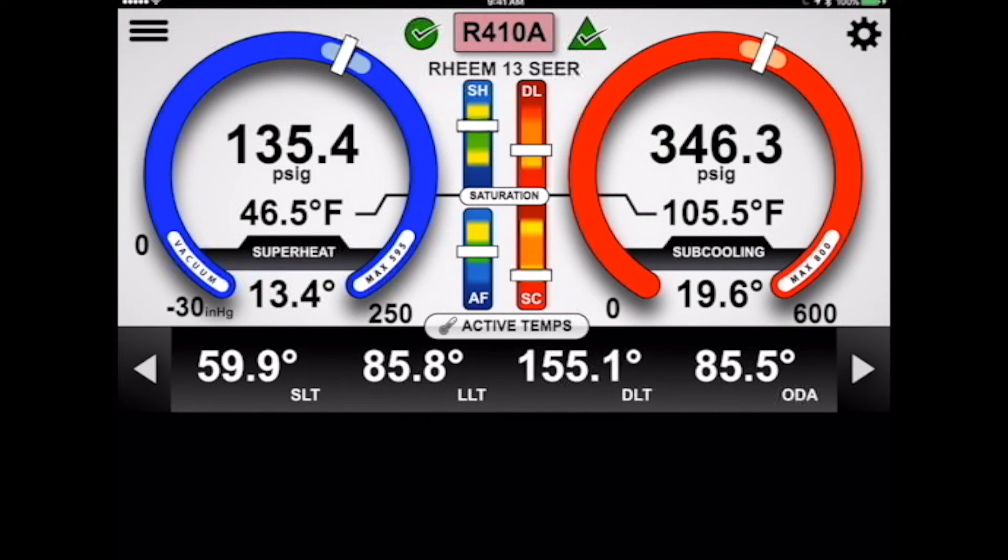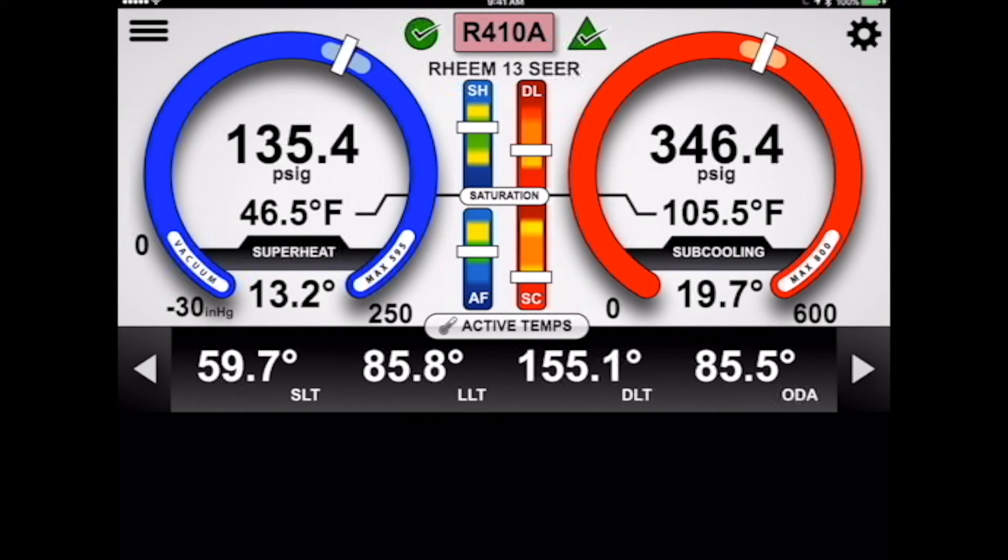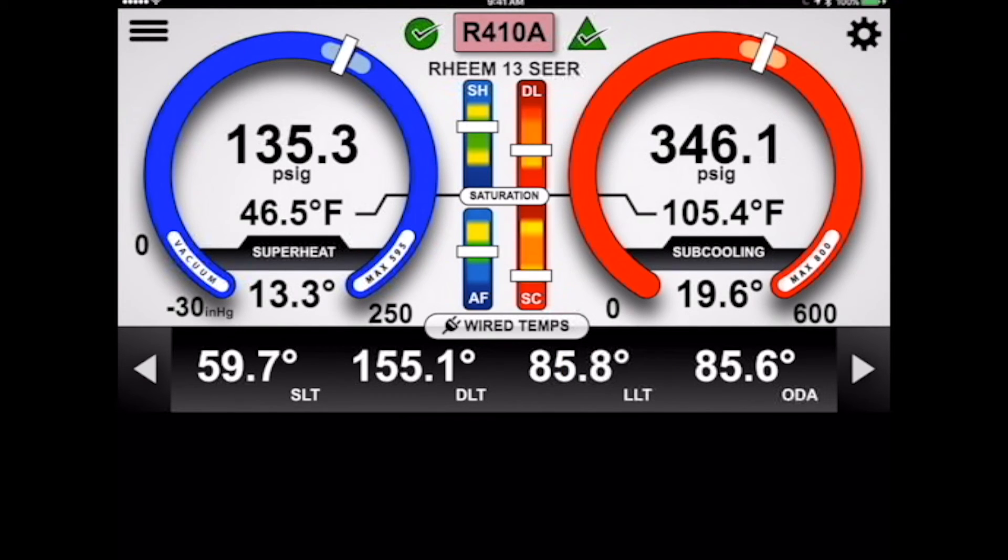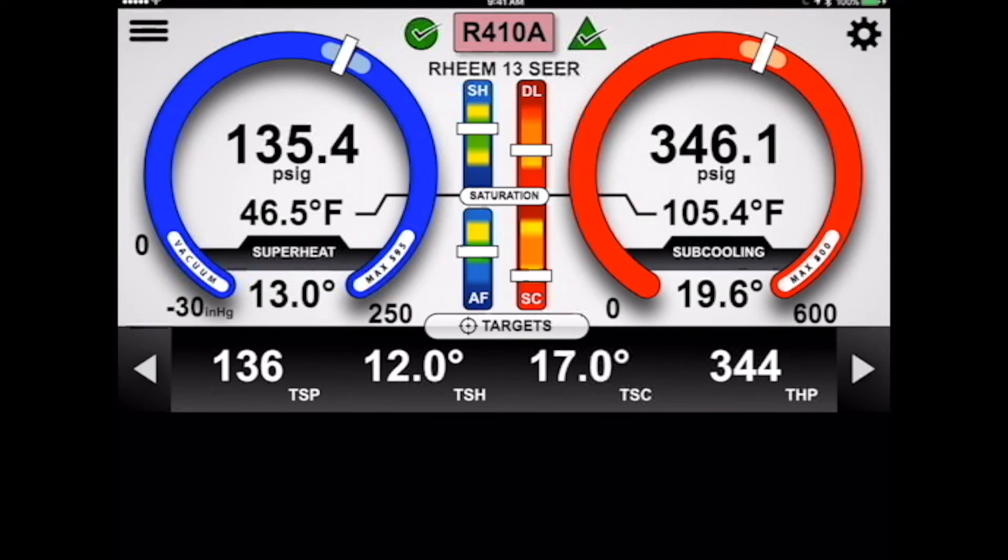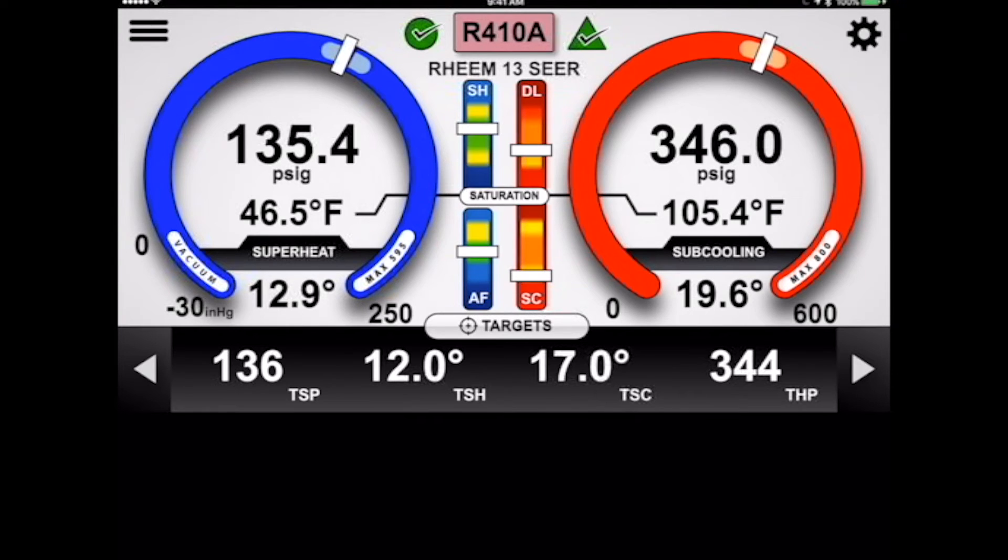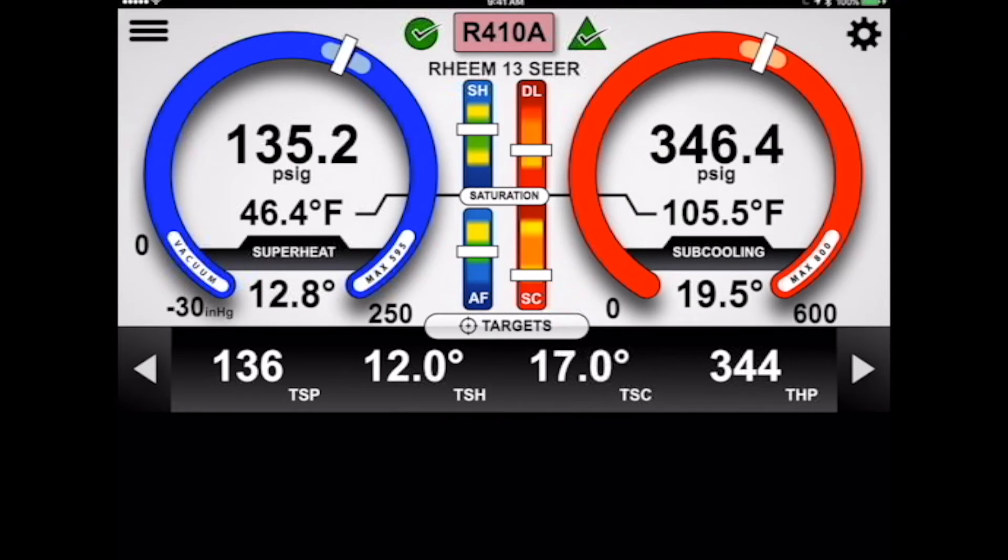So now if I scroll across the bottom line here, you can see now that we have targets. So my target suction pressure is 136, my target superheat is 12, my target subcooling is 17, my target high pressure is 344. And all these targets are being calculated off that basic profile.